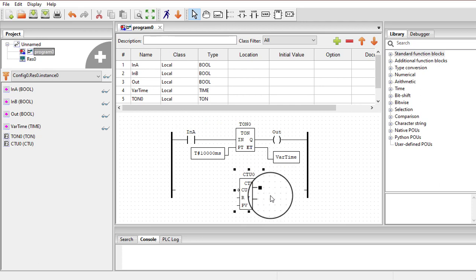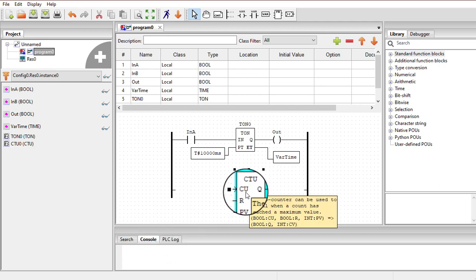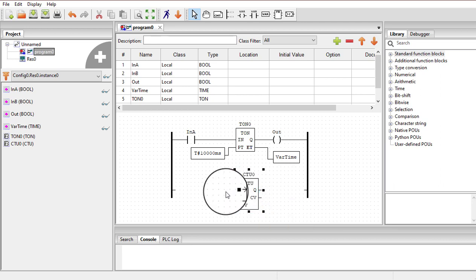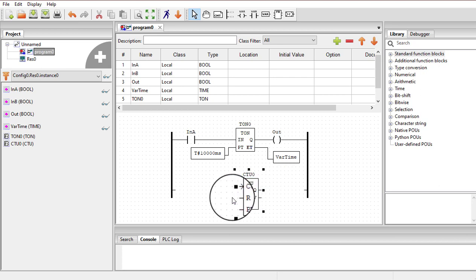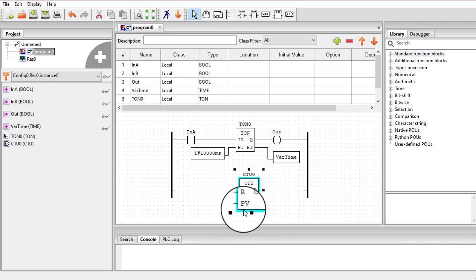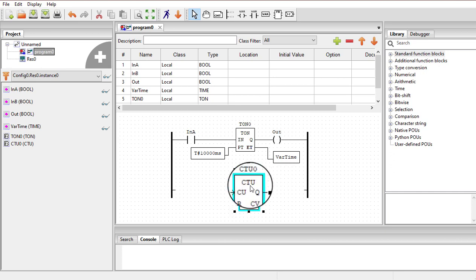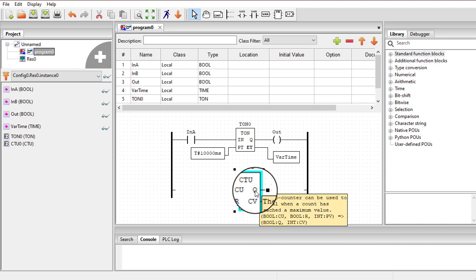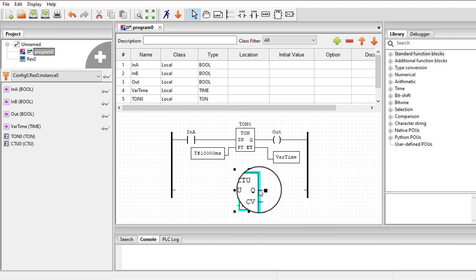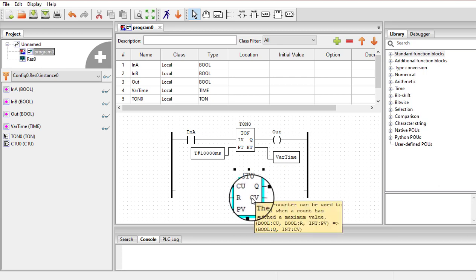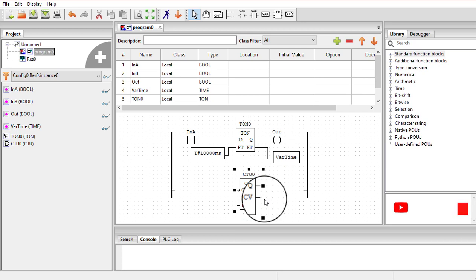This counter has 5 terminals. The first terminal, CU, receives the pulses to be counted — whenever a false-to-true transition occurs at CU, the counter increments by 1. The R terminal is for reset — providing 1 here resets the counter. The third terminal is the preset value, for how far you want the counter to count. For example, if you want it to count up to 5, apply 5 here. The Q pin is the output — when the counter reaches the preset value, Q goes high and turns on any attached output. The last terminal shows the current count value.